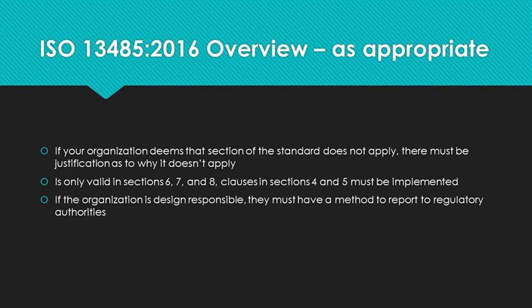Reporting to regulatory authorities is a clause in section 8. However, if the organization is design responsible, then they must report to regulatory authorities, so that clause cannot be deemed not applicable, even if they are a component manufacturer. Now, the important thing for us today is that all the requirements in section 4 and 5 must be implemented. None of them can be excluded or determined as not applicable.